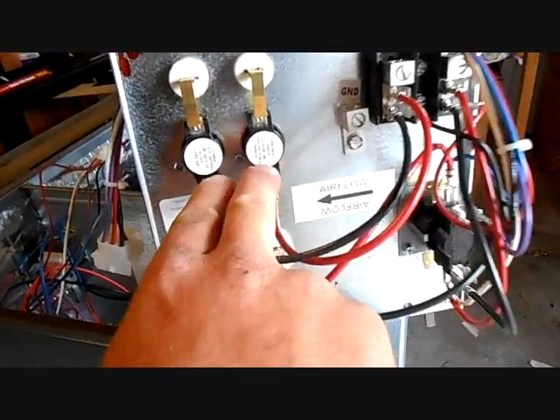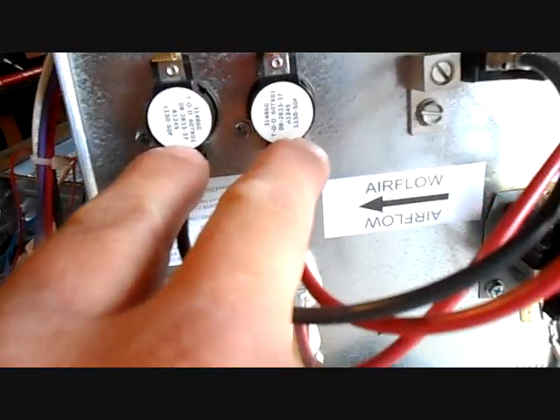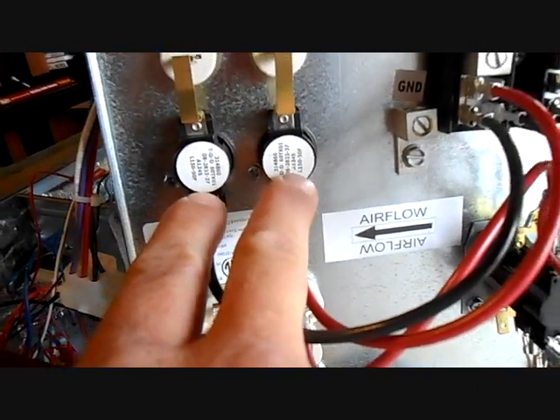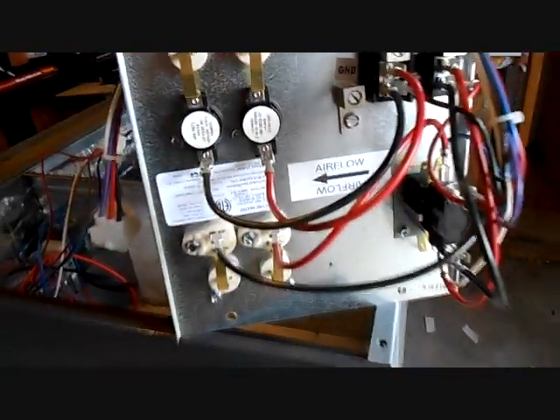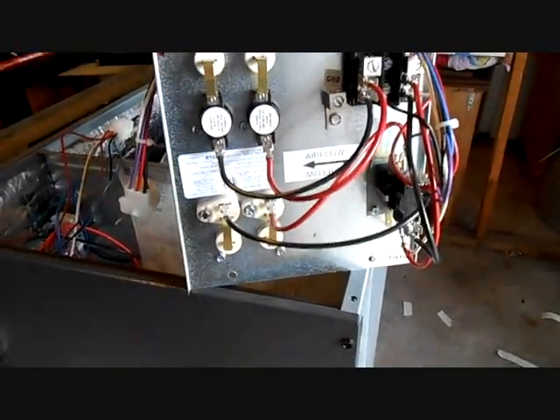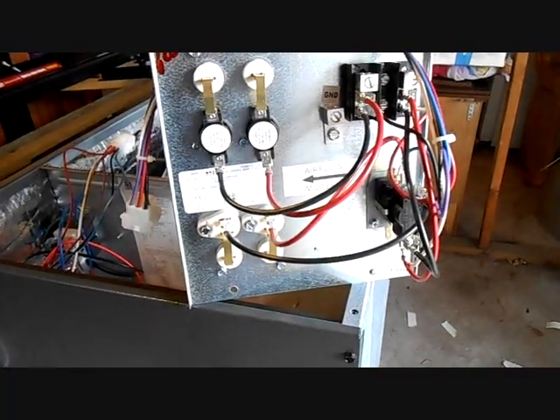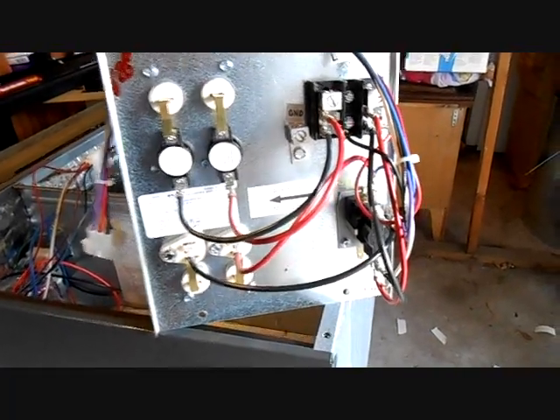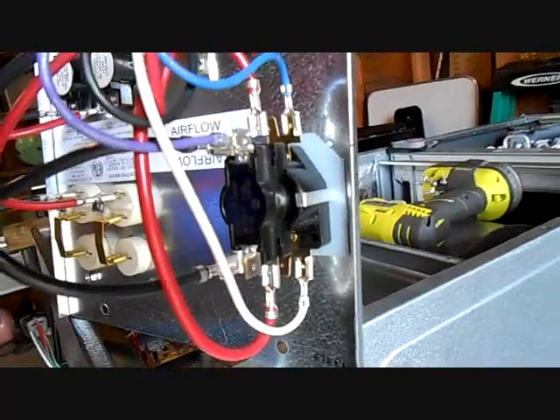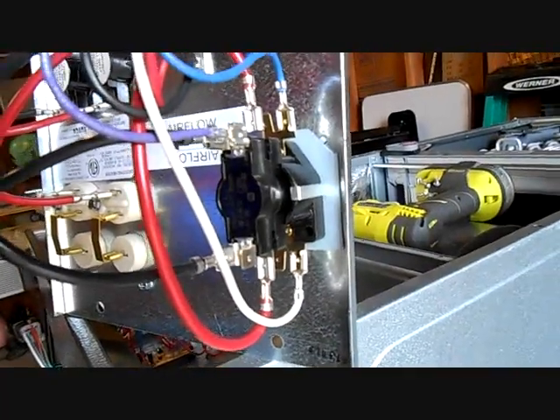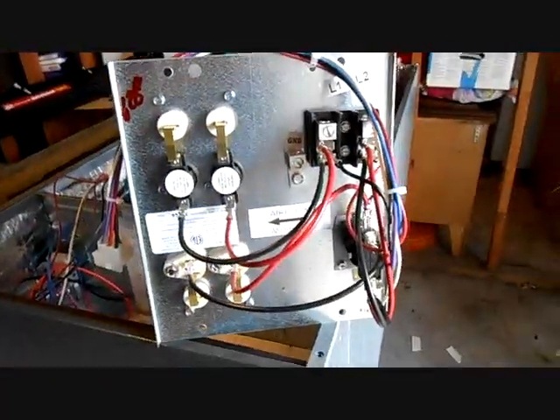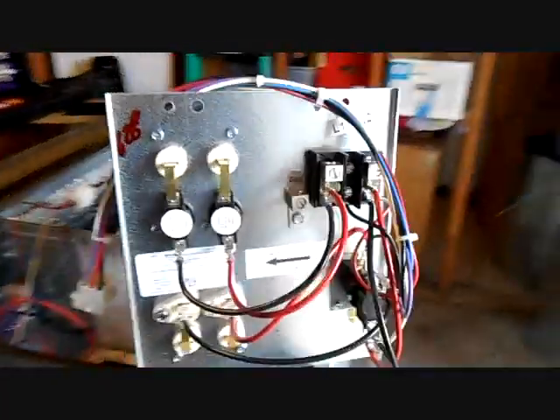Limit switches right here. L150. So they trip out at 150 degrees. Over here is a stack sequencer. 10KW. Sort of standard fare for the heaters.